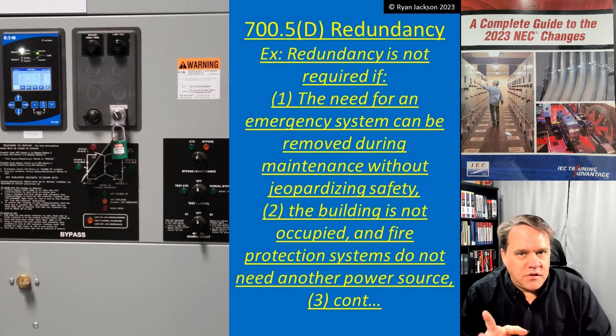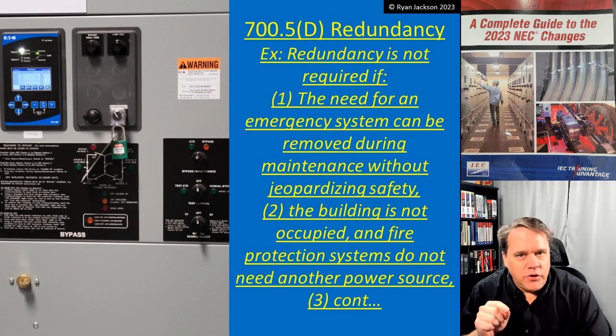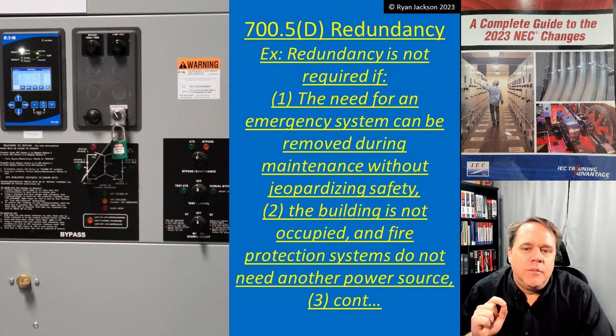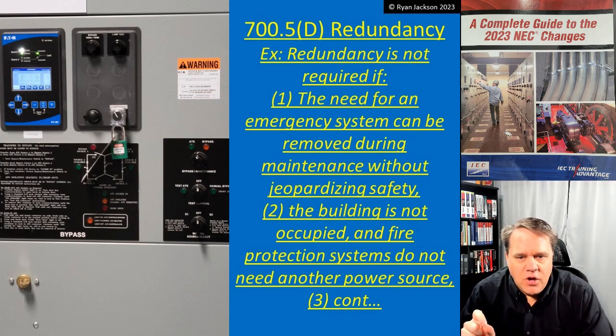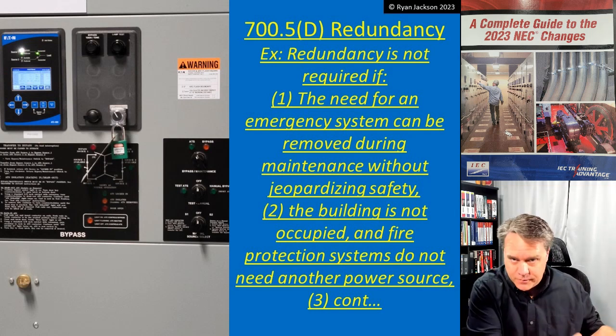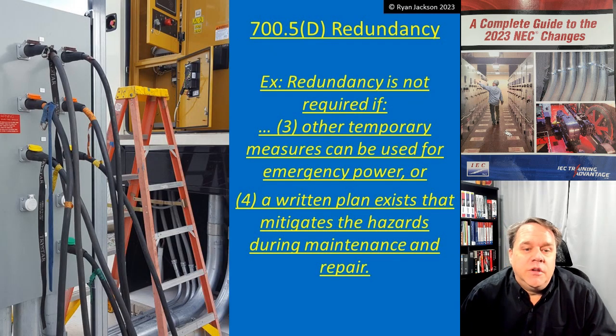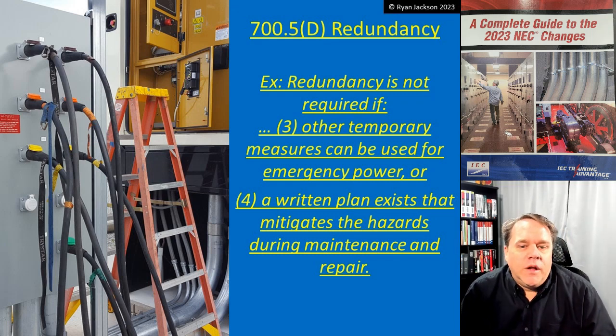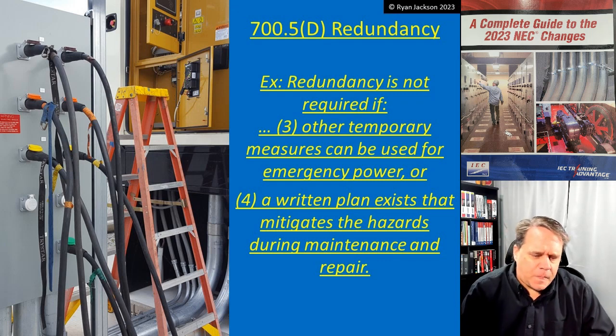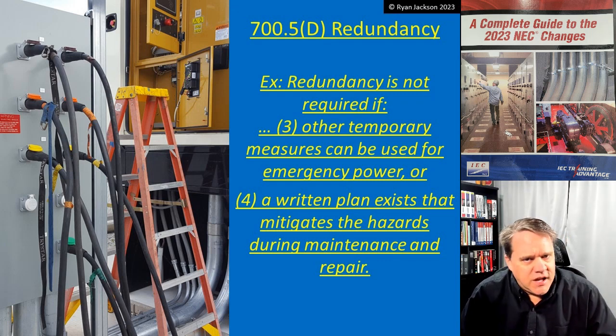Now, this redundancy requirement is not required if the need for an emergency system can be removed during maintenance without jeopardizing safety, or if the building is not occupied and the fire protection system like a fire pump does not need another power source, or if other temporary measures can be used for emergency power, or if a written plan exists that mitigates the hazards during maintenance and repair.